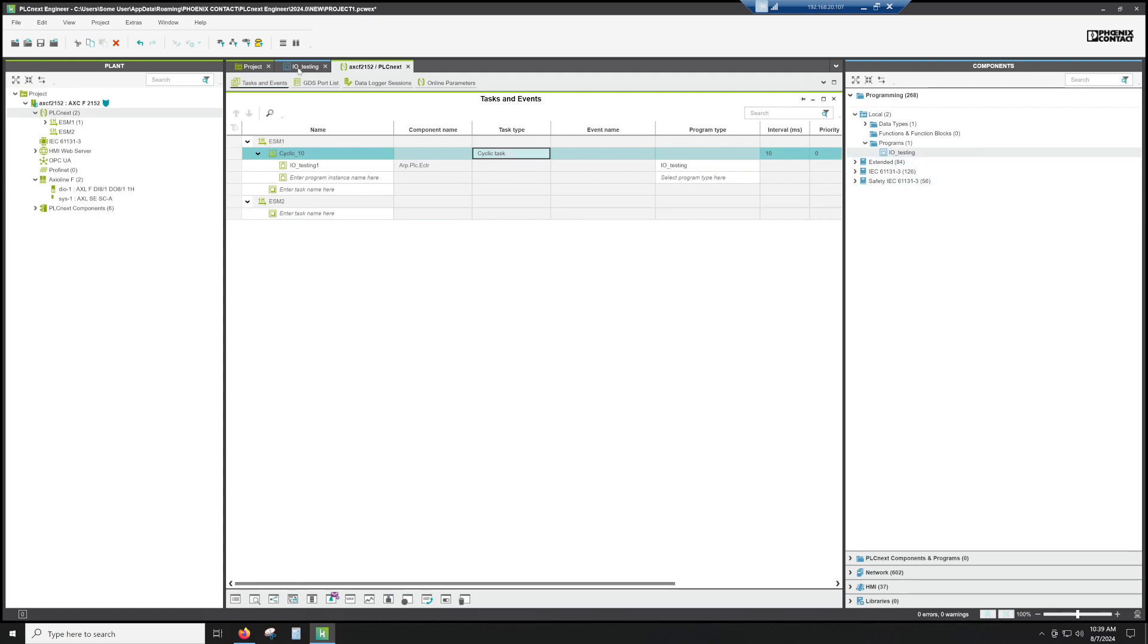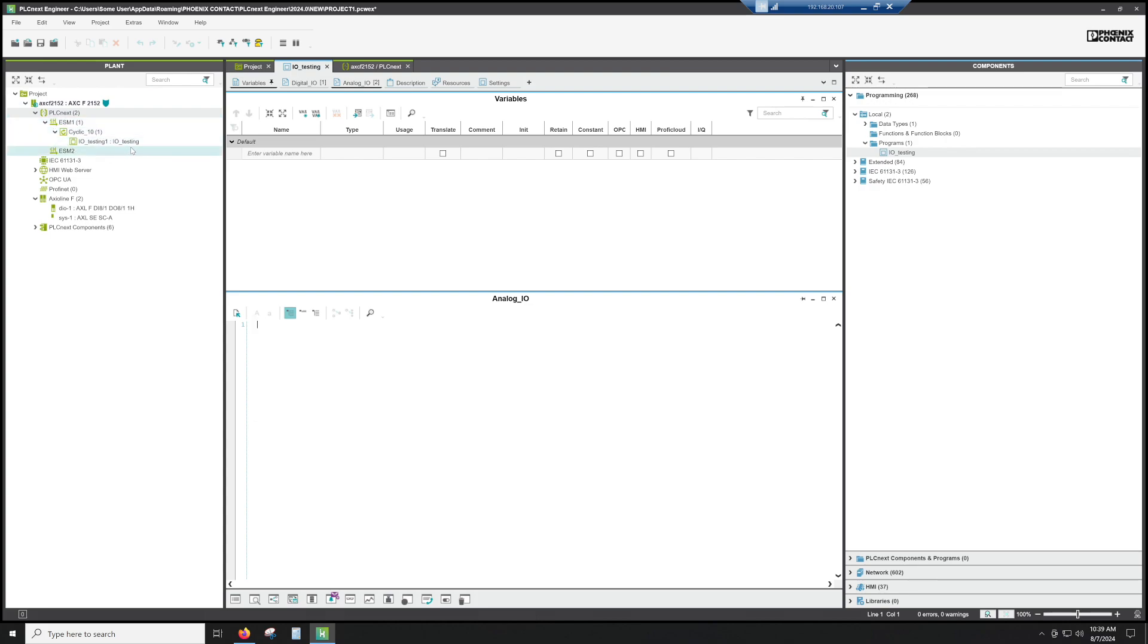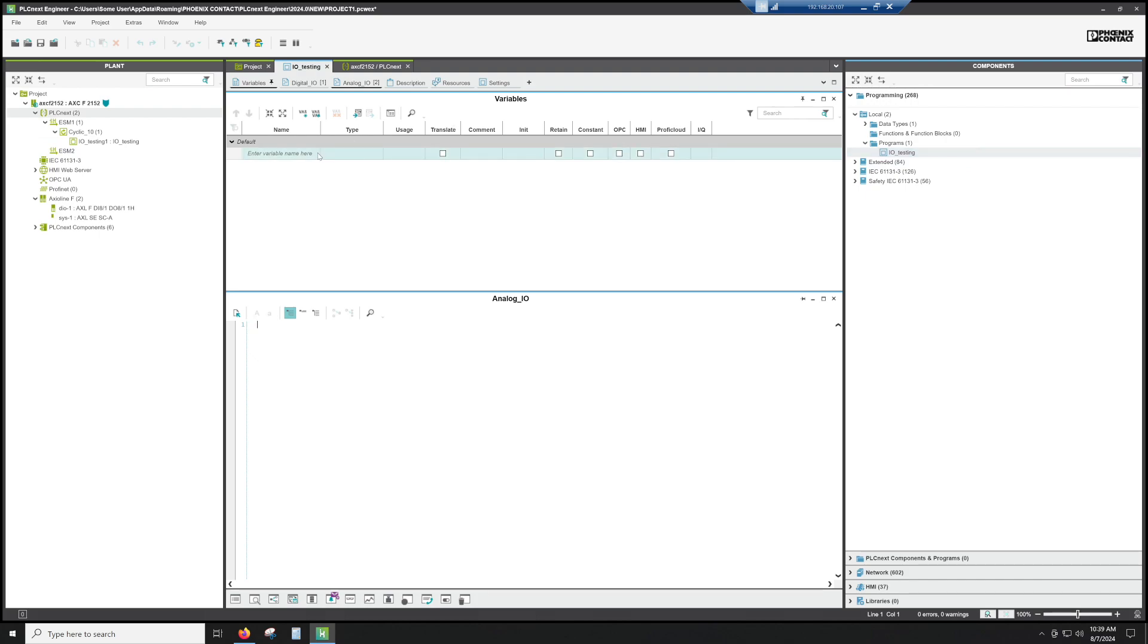So we created a program, we created some worksheets inside the program, and then we attached that program to one of the two cores doing the processing on the PLC next. If you don't have your program in one of the cores when you're working on it and you go to make external variable types, they don't move over to the external variable list. So you have to put them in manually. So I always try to get my worksheets and my programs into the task schedule so that when you do create an external variable, it does get put into the variable list.